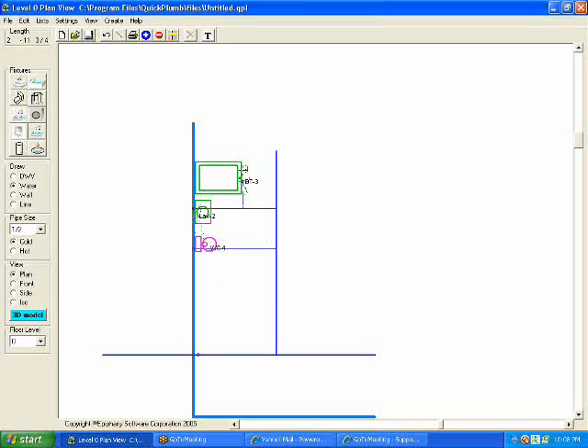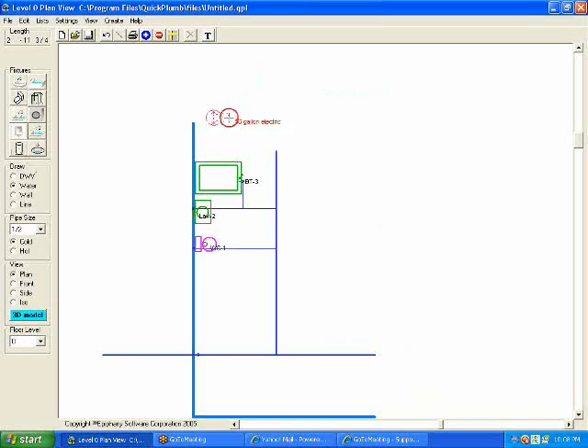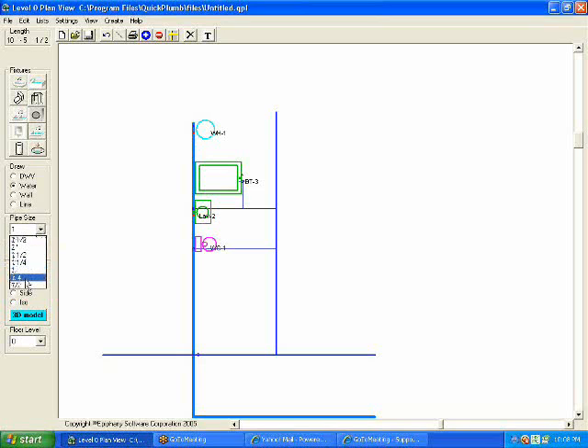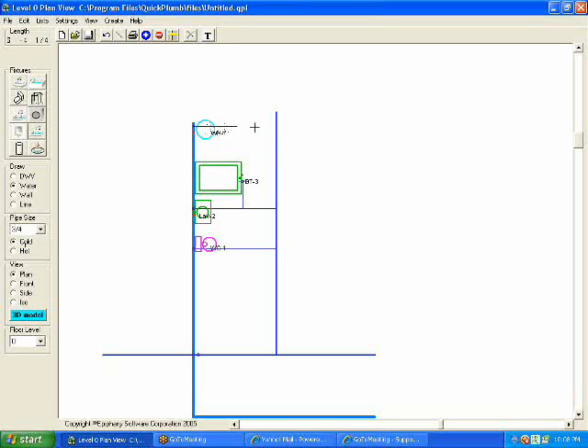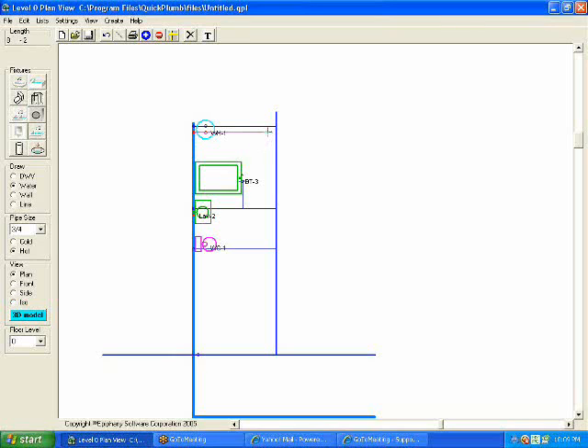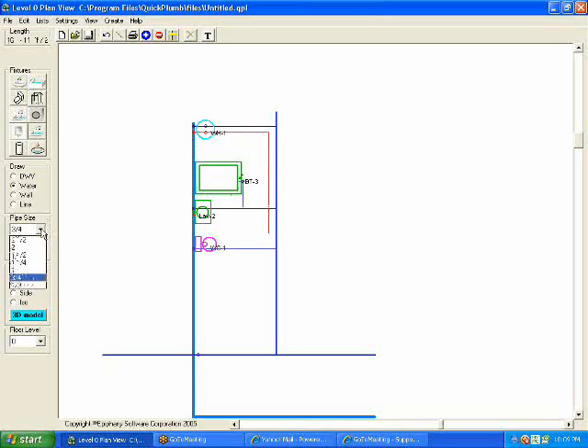Now, in order to connect hot water, I need a water heater. I'll just place a water heater right here on this wall. A water heater has to have a cold water supply. Typical residential water heater would have a three-quarter inch supply. Click anywhere on the heater with cold selected and drag that pipe over to the branch. That connects several pipes. It connects the vertical pipe to the heater, and it also gives me a hot water stub out that I can edit, move around, and carry it wherever I need to.